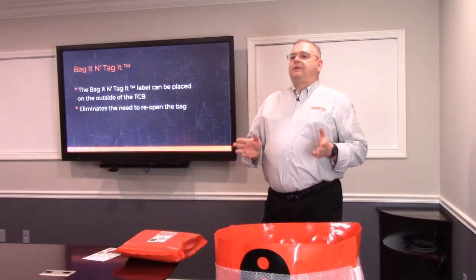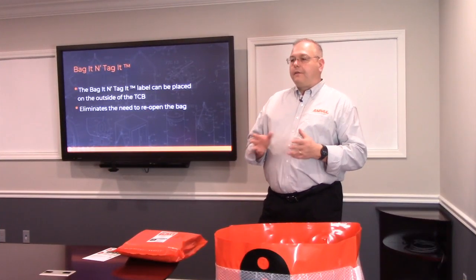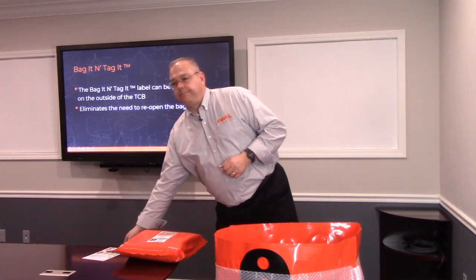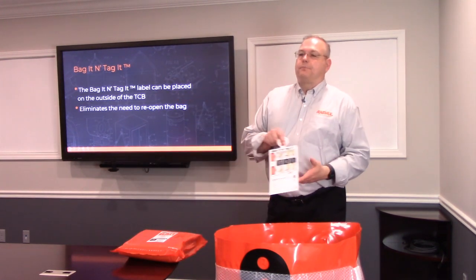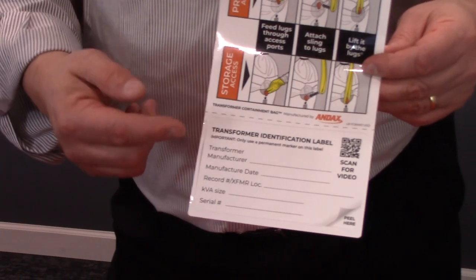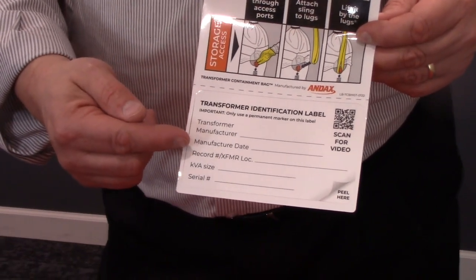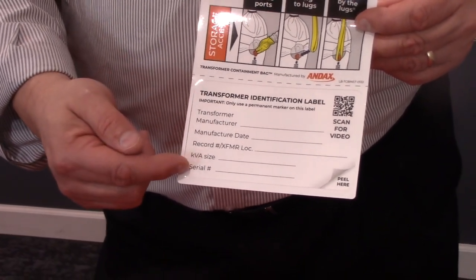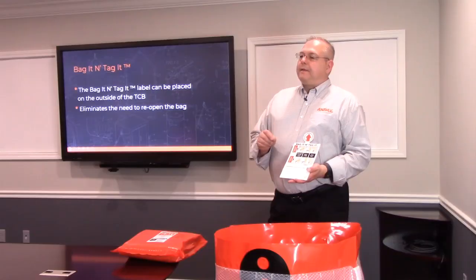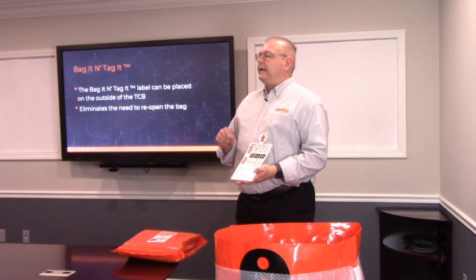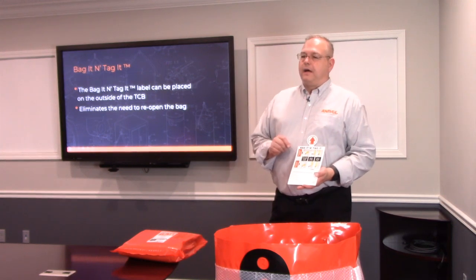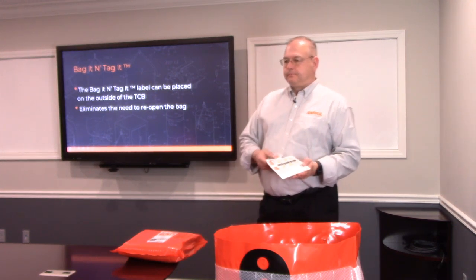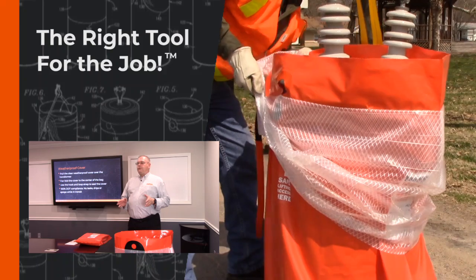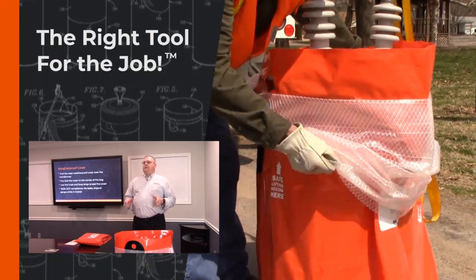This is a good time to complete any documentation or other steps required by your utility before getting ready to transport the transformer. The included Bag It and Tag It identification label can be placed on the outside of the TCB, eliminating the need to reopen the bag and reducing exposure to any oils once the cover is pulled up and fully contained. To fully contain the transformer, remove your sling and pull the cover up and over the transformer.